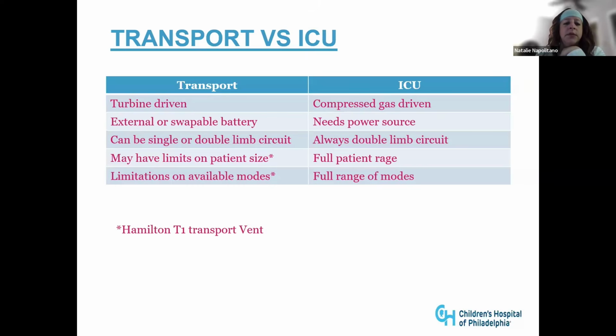And you have a limitation on the modes that you have available. You're not going to have these adaptive modes in most situations on your transport ventilators. But in the ICU ventilators, they have all the bells and whistles. If you purchase it, they have the full range. Oftentimes, they will offer an option that's just an adult mode. But if you want the neonatal and pediatric modes, then you have to pay extra for that software in that full patient range. There is one that's kind of an exception to this, Hamilton's T1 transport ventilator.